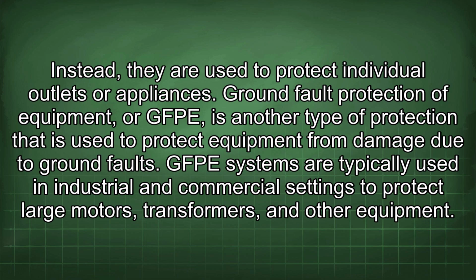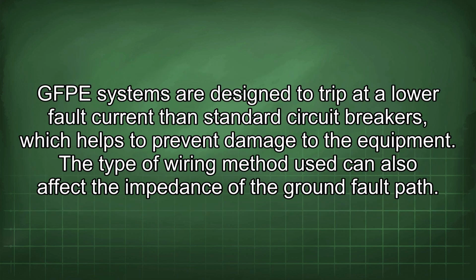Ground fault protection of equipment, or GFP, is another type of protection that is used to protect equipment from damage due to ground faults. GFP systems are typically used in industrial and commercial settings to protect large motors, transformers, and other equipment. GFP systems are designed to trip at a lower fault current than standard circuit breakers, which helps to prevent damage to the equipment.